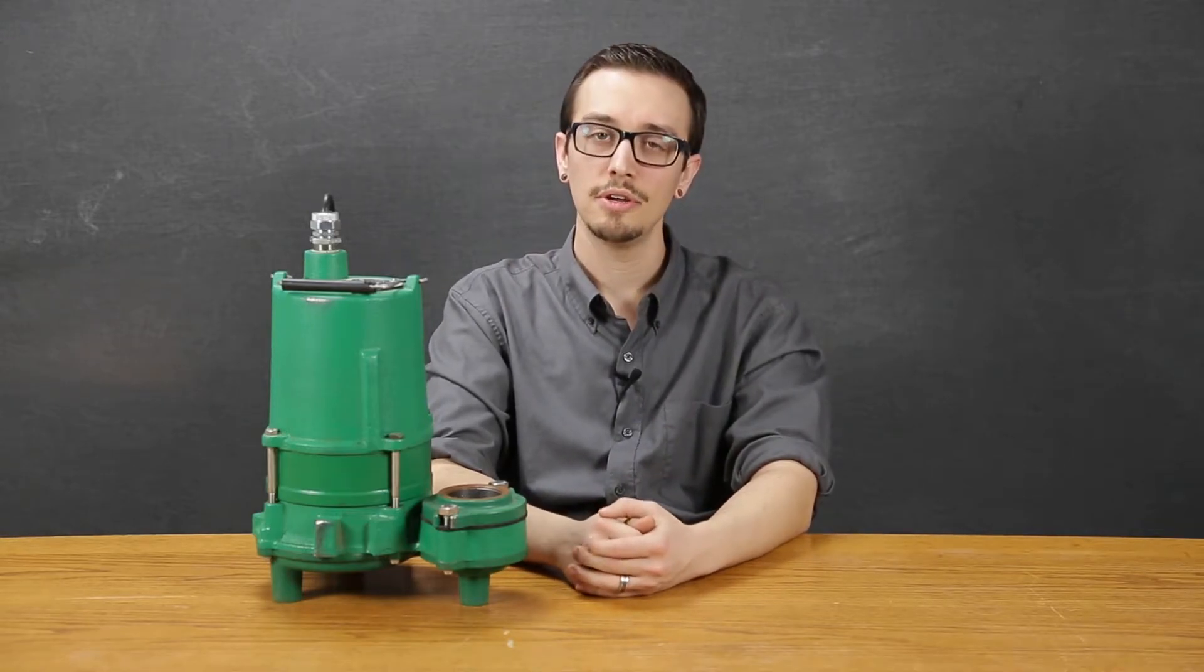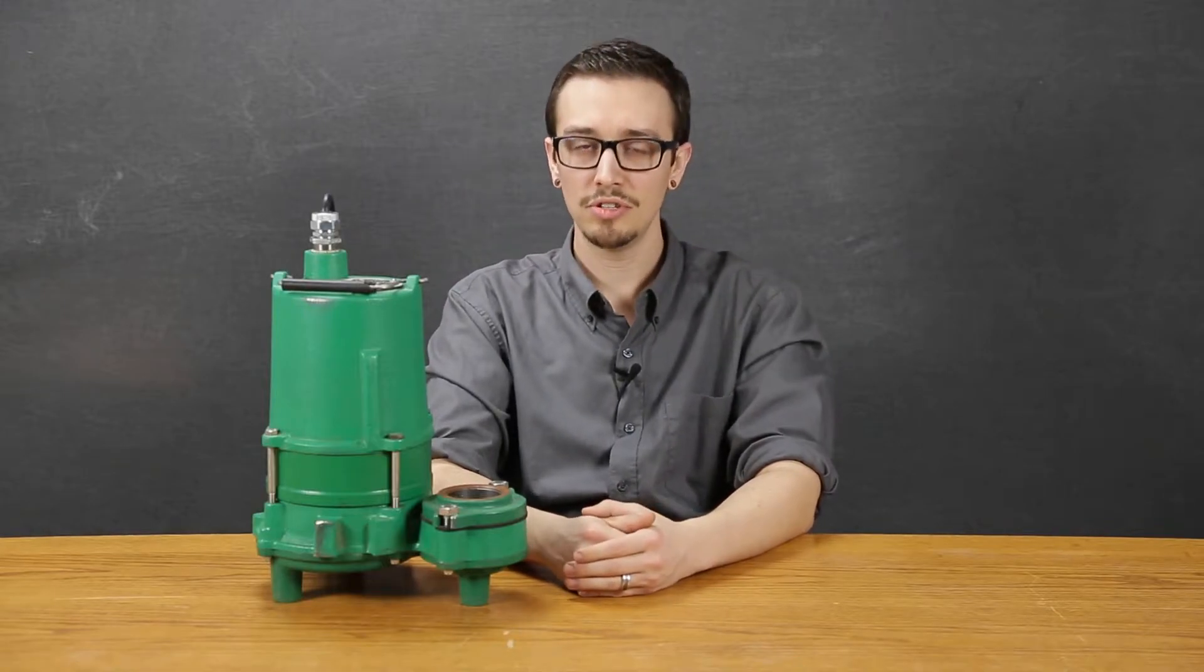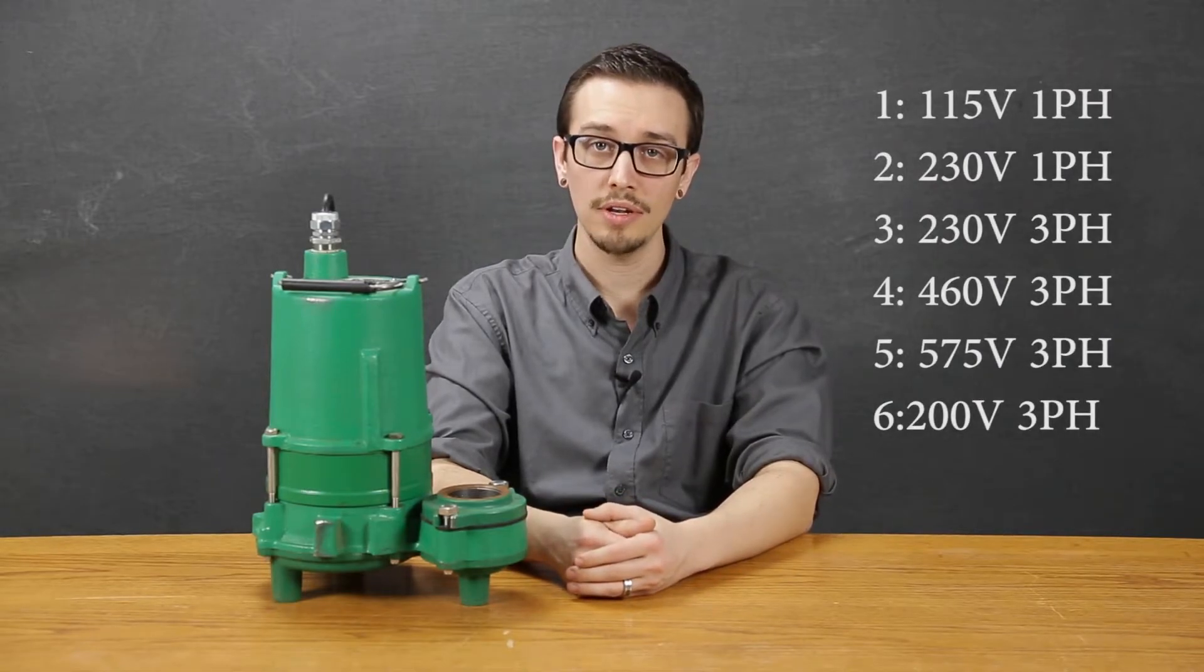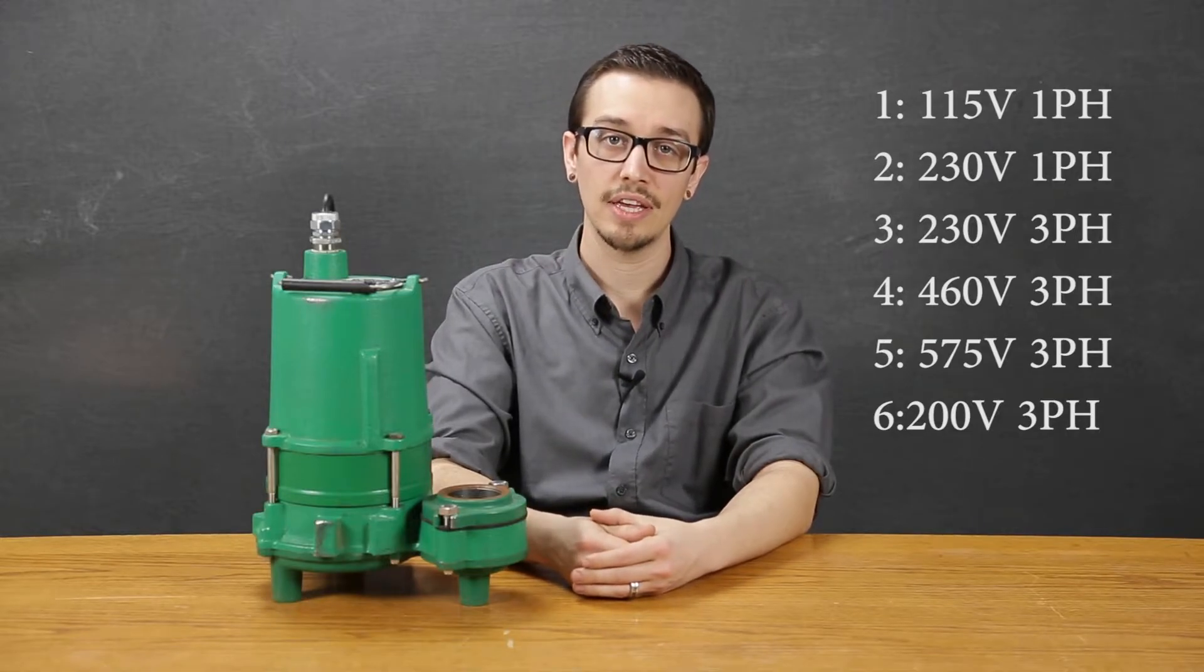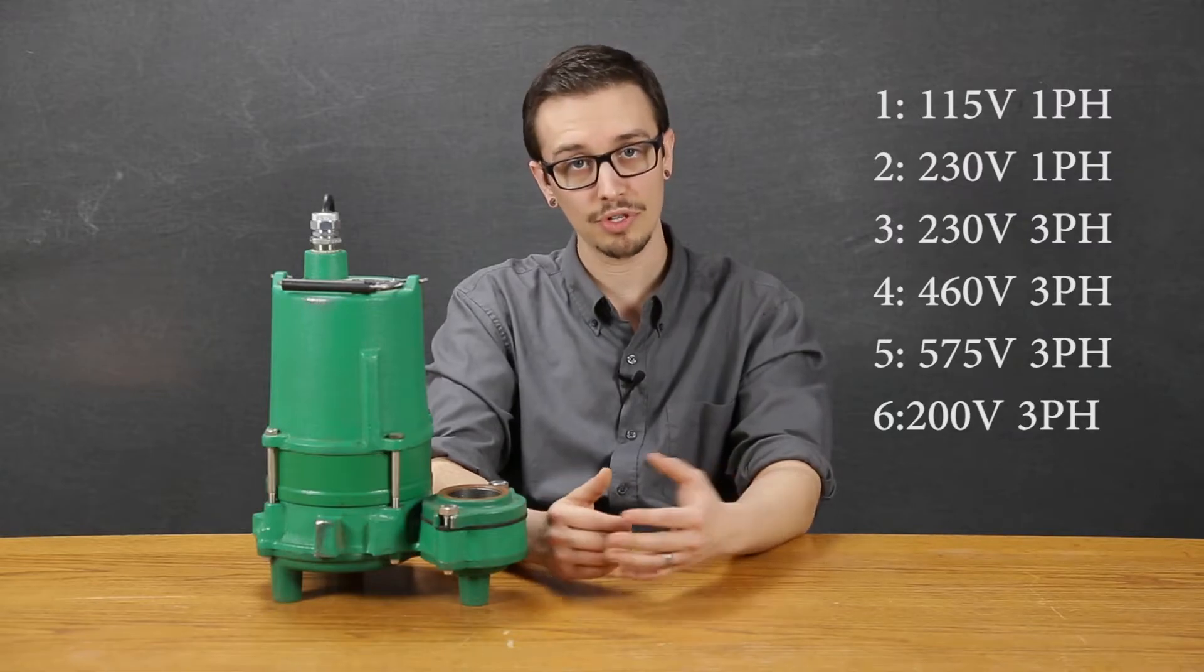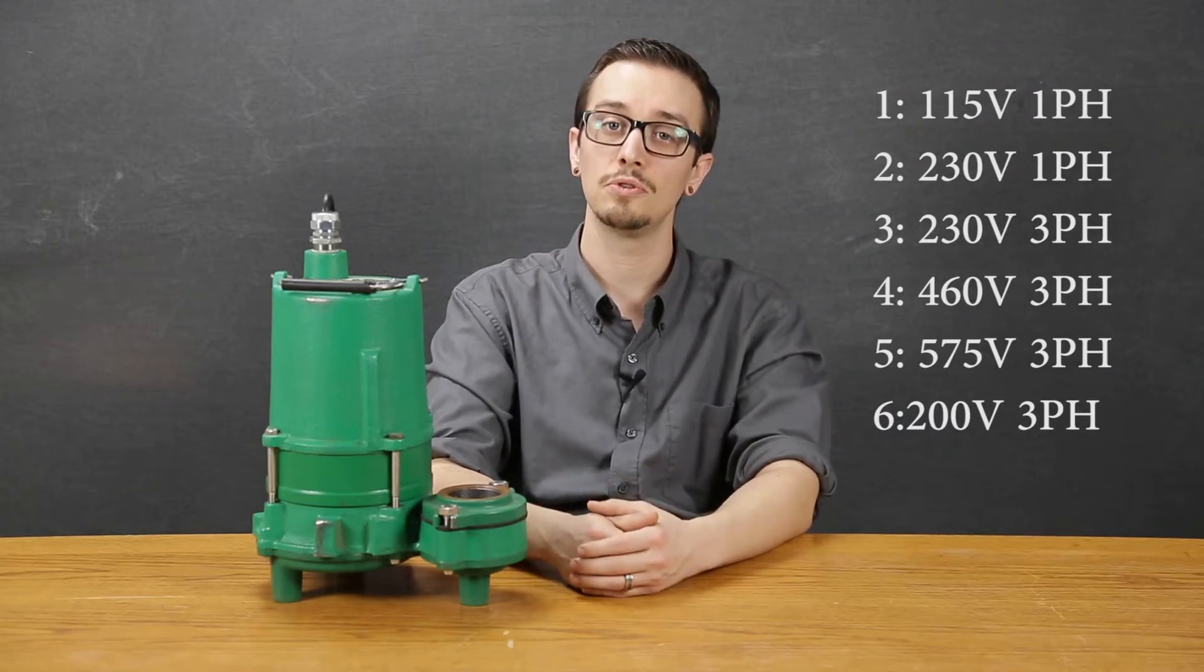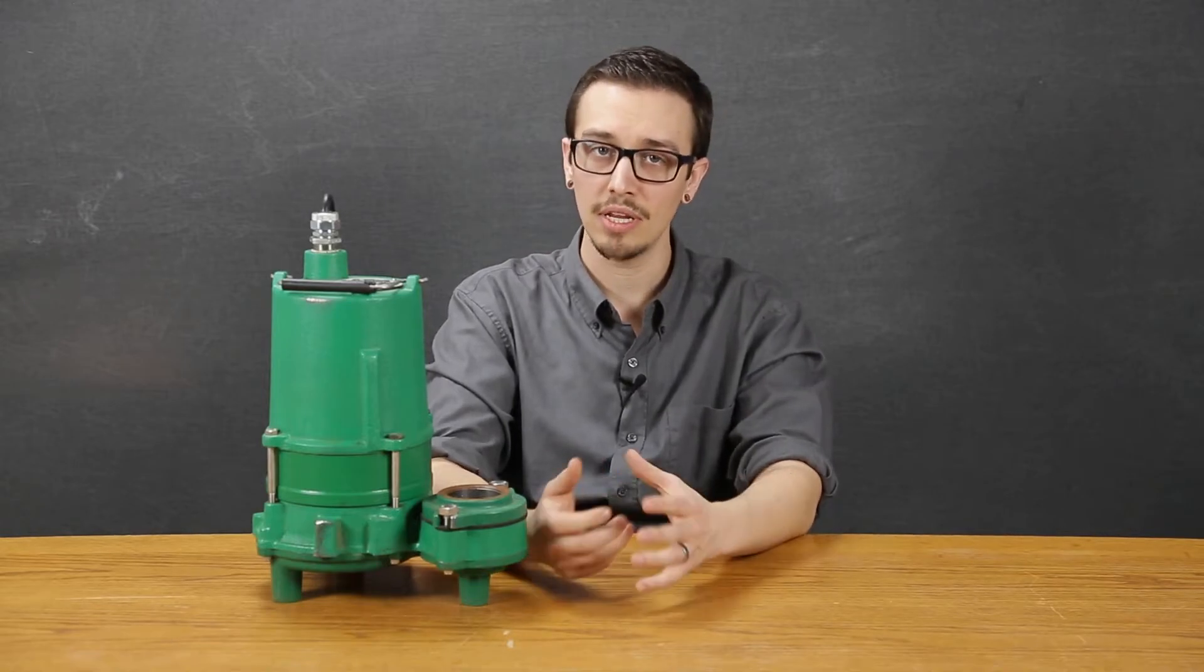When it comes to identifying the voltage, you simply need to look at the model number. On this pump, the voltage is indicated after the H in the model number. A 120 volt would be a 1, a 230 volt single phase would be a 2, and then you would have a 3 for 230 volt 3 phase, a 4 for 460 volt 3 phase, 5 for 575 volt 3 phase, and a 6 for 200 volt 3 phase.